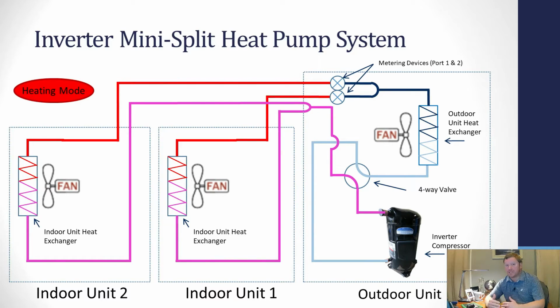So now you're looking at that potential of 7 degrees from the set point. So I might set a unit for 70, have it target 73.5 up at the return, which is up by the ceiling, but then the unit doesn't actually shut the fan off until the return is 77, which means down where I'm sitting it's 74. Well, I wanted a set point of 70. So now I'm 4 degrees too warm. And this does cause comfort complaints. This isn't always a problem, but the more indoor units you add to a mini-split, the higher the risk for these problems is.